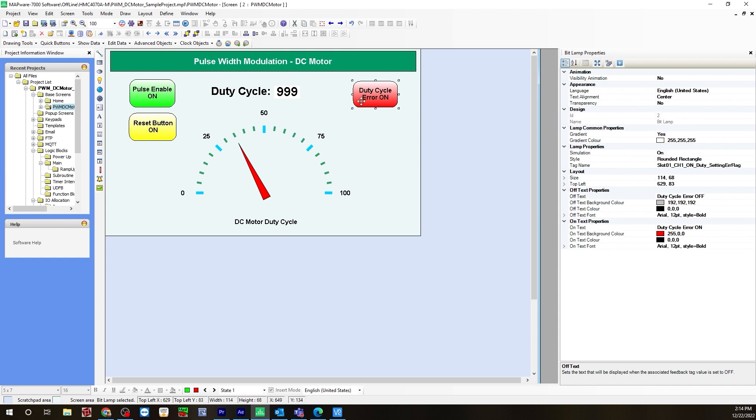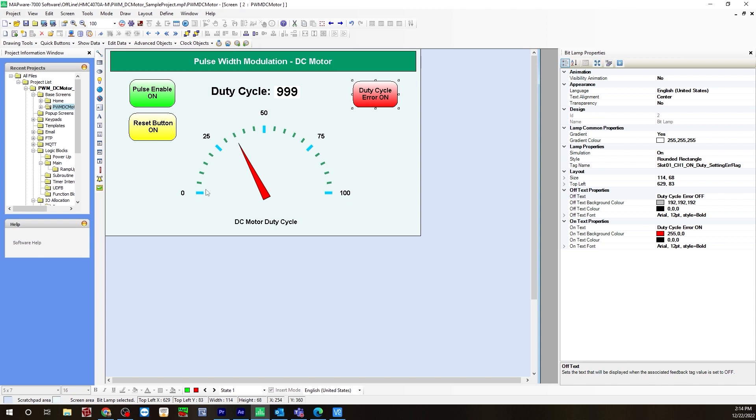For the duty cycle error flag, I have this on here. If the duty cycle hits zero or 100, it will turn this on. If it's between 1 and 99, it'll not trigger this. Keep in mind that 1 will not turn the motor off. To turn the motor off, you'll need to turn the pulse enable off. For this bit lamp, I have the on text saying duty cycle error on, and the off text is duty cycle error off. I'm using the tag name slot 1 channel 1 on duty setting error flag.